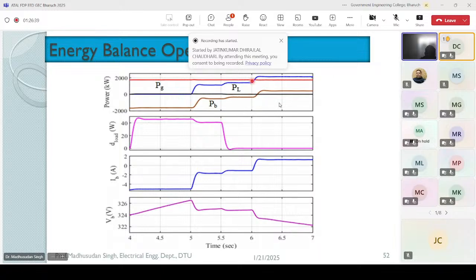And at this moment, you see, when the load power exceeds the rated power of the generator, then the battery is supporting the load. So you see that the load power, the battery power is now positive. So the battery along with the generator is able to meet the load. So this is the profile of your power balance, how the power is maintained, and hence the frequency is maintained in this system.